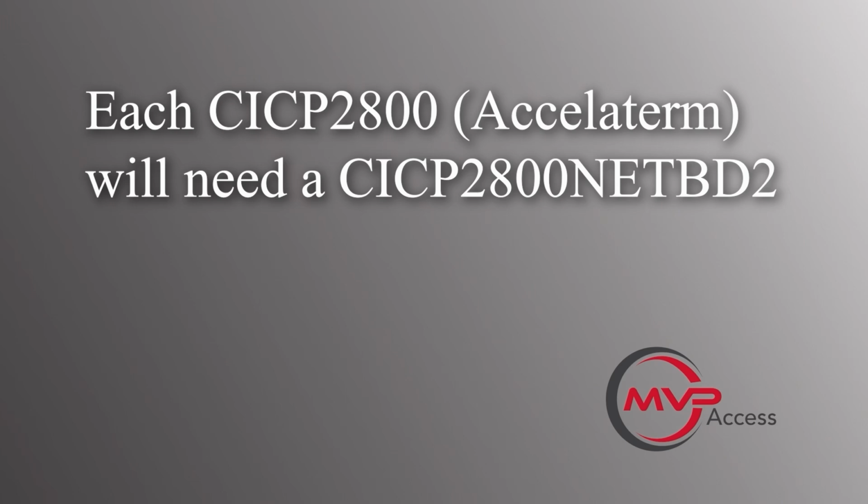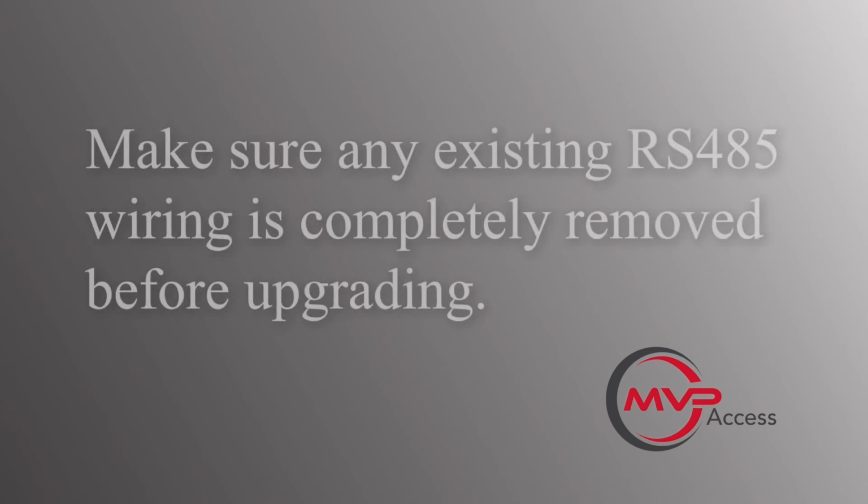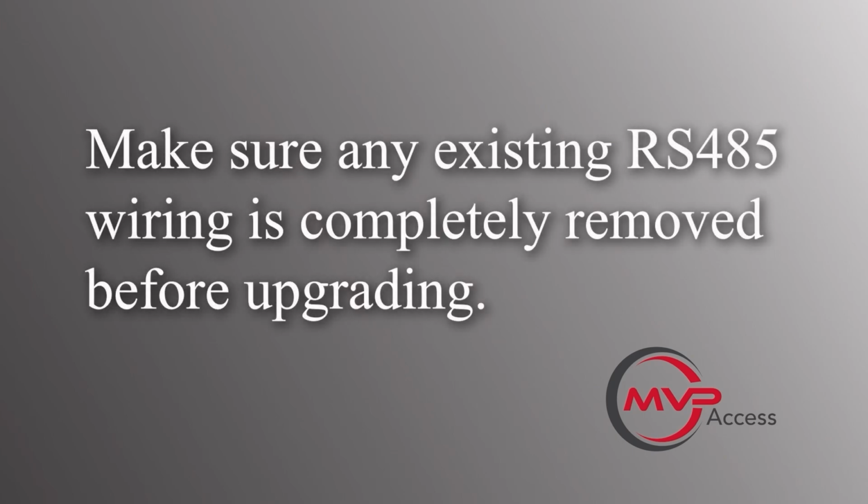Each Accelaterm will need a cloud-ready CICP2800 Netboard 2, replacing the CICP18ACC netboard. Each panel will also need to be connected to the customer's LAN/internet. RS-485 is not supported. Also, if this is a migration, please make sure that you have any RS-485 wiring removed permanently. This should be done before continuing.